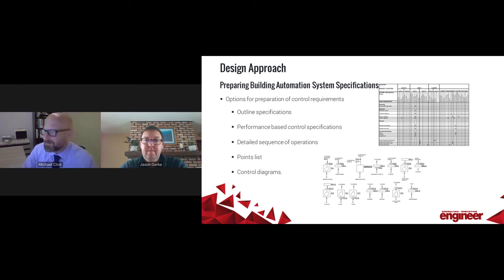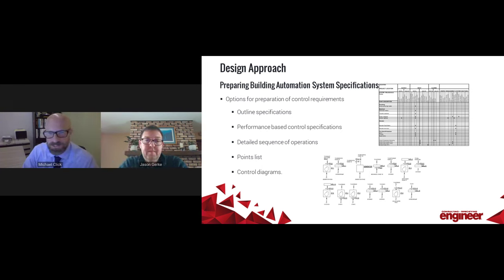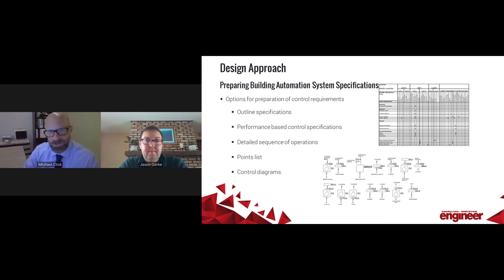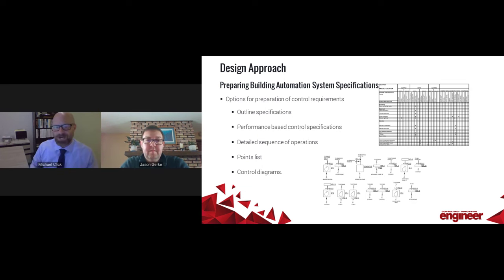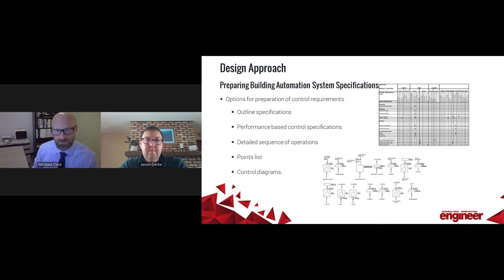A lot of times on our design documents we will list a points list. It's very important to have one so that you can show the analog inputs, analog outputs, digital inputs, and digital outputs you're expecting for your project. Along with that, you can also identify alarming for particular points that aren't working correctly. It gives a graphical user interface for a controls contractor to work from and make decisions in the field when making those programming changes.